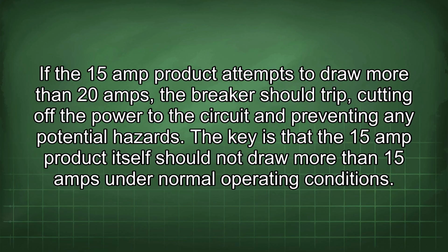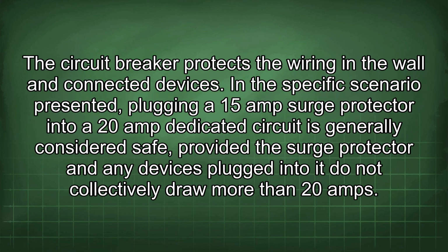The key is that the 15 amp product itself should not draw more than 15 amps under normal operating conditions. The circuit breaker protects the wiring in the wall and connected devices. In the specific scenario presented, plugging a 15 amp surge protector into a 20 amp dedicated circuit is generally considered safe, provided the surge protector and any devices plugged into it do not collectively draw more than 20 amps.